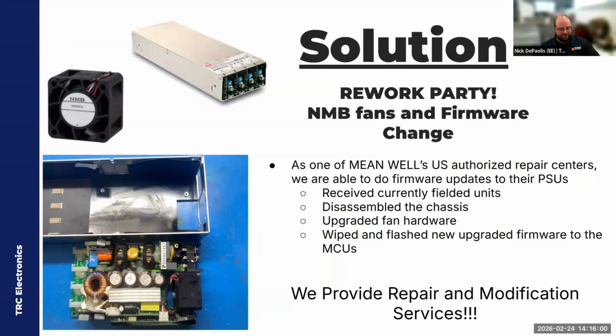I was going to say the way we also provided this was essentially we provided them an initial batch of the upgraded units with supporting test data that we developed in addition to the factory. We worked with them to develop our own in-house validation to get the client's buy-in before we started upgrading all their hundreds of units. So what that basically looked like was we took a non-modified unit, took baseline measurements with an uncalibrated decibel meter, and then we compared that to a modified unit, several of them to kind of build up that control group versus the test group.